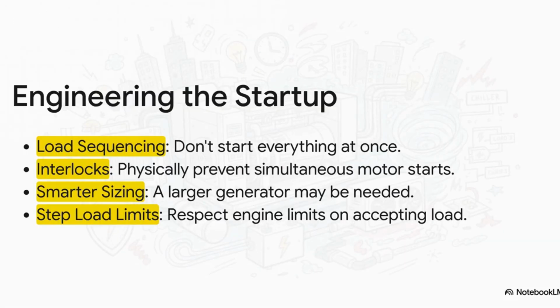So how do engineers prevent this total catastrophe? Well, they do it through some really clever electrical choreography. That control system, that brain, is programmed with a very specific startup sequence. It staggers the big loads, bringing on the fans, then the pumps, then the chiller, sometimes using physical interlocks to make it impossible for 2 big motors to start at once. It's like an electrical ballet, all designed to manage that surge and respect the engine's limits.